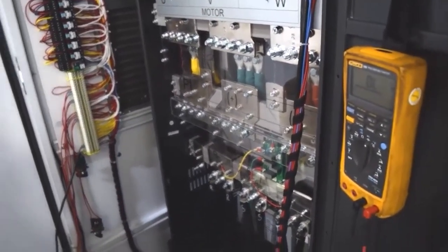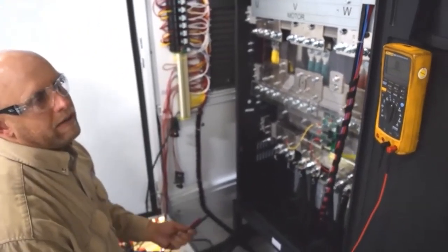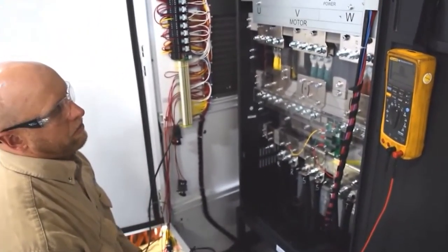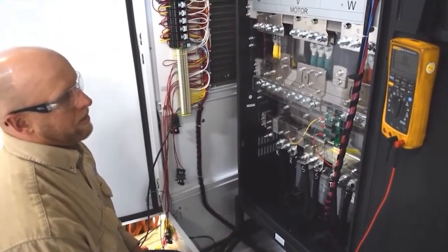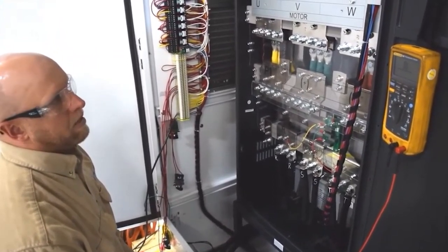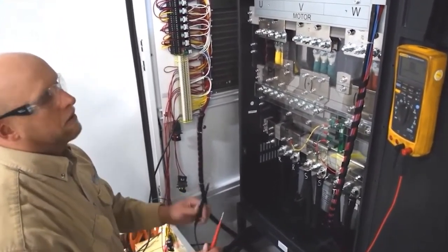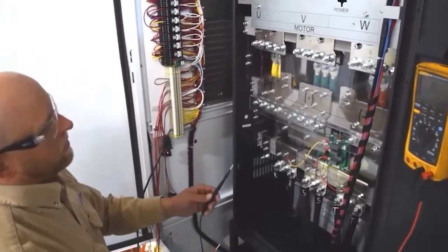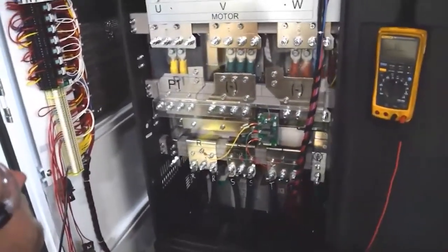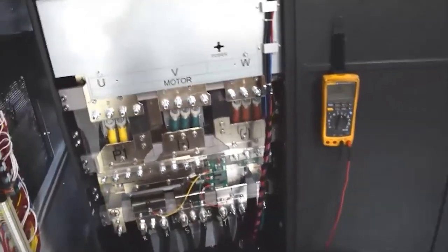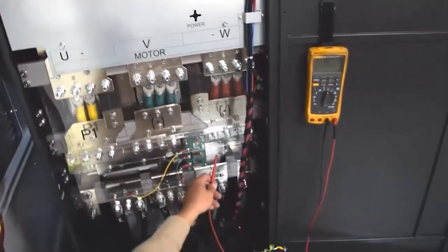One thing to keep in mind when you do this reading, you usually are going to measure somewhere between about a 0.2 and a 0.5 on your diode rectifier or your incoming. And then on the outgoing, usually it's a little bit lower than your incoming, but it is still about the same. So it's somewhere between a 0.2 and probably a 0.4 output. Now I'm going to go ahead and measure the transistors.